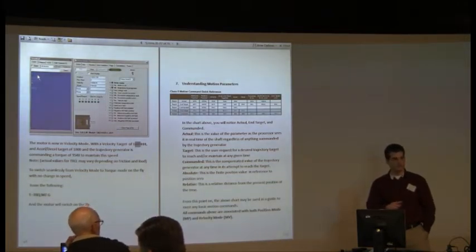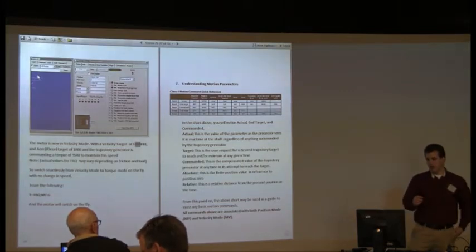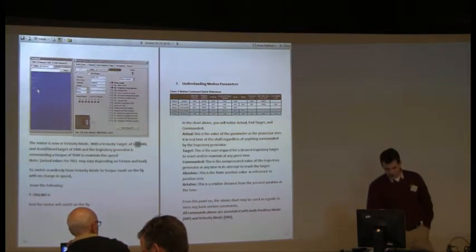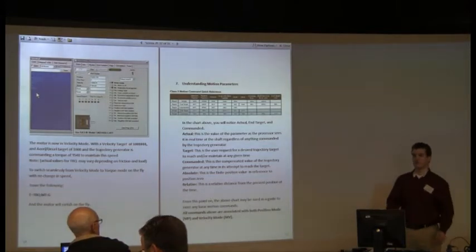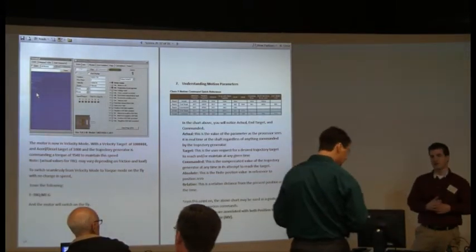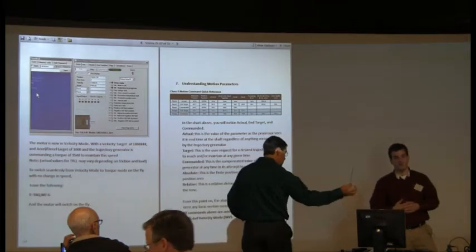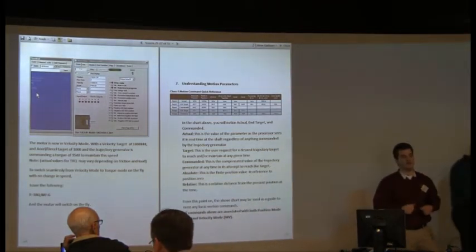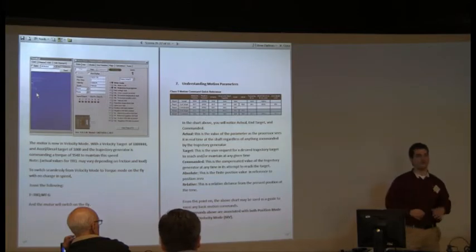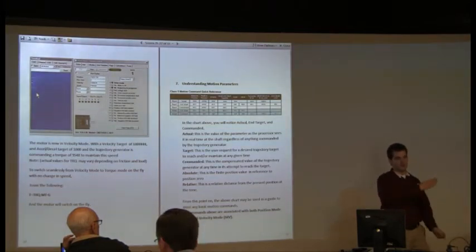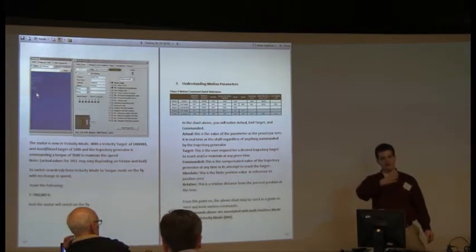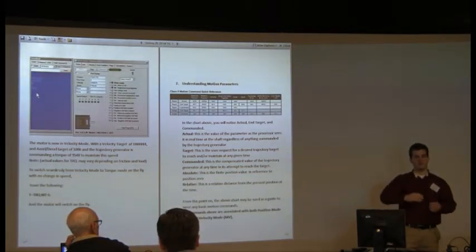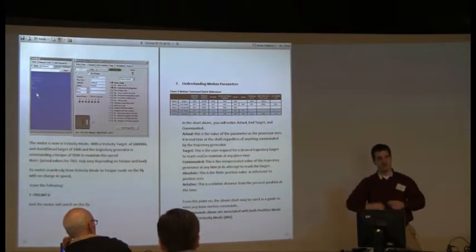Are we spinning? Everybody spinning? So what we're going to do now is we're going to jump from a velocity move into a torque move. We're going to make the motor stop caring about what its position is and what its exact velocity is. For example, if you're doing a controlled collision in something like maybe a home to hard stop, you don't want to get an error. So you start a velocity move, and then you have it stop caring where it is. Because in a velocity move, it cares where it is. It has a position that it knows it should be at as time goes on, and it strives to maintain that position.